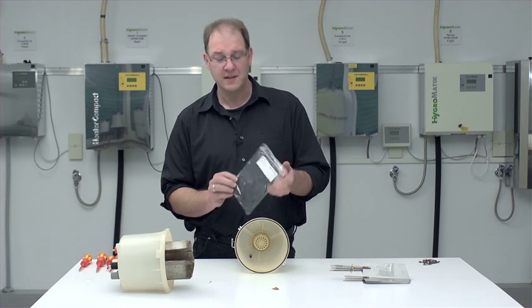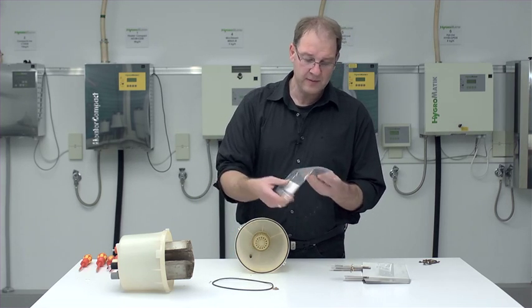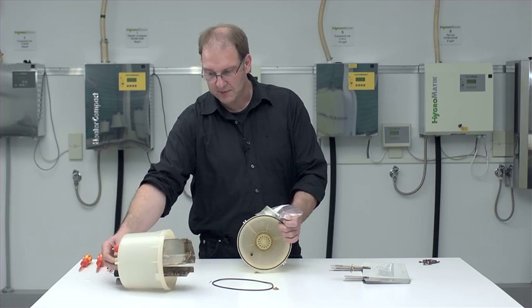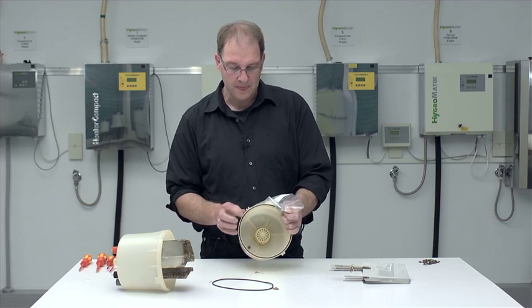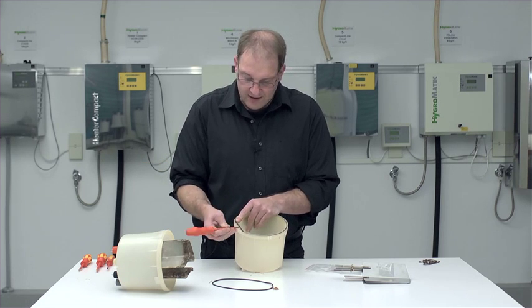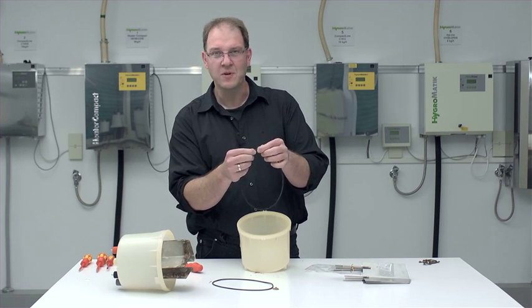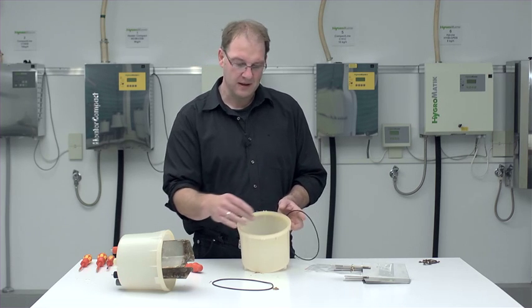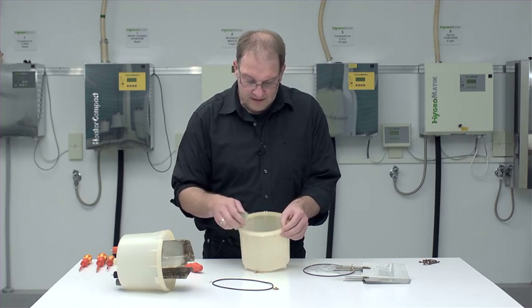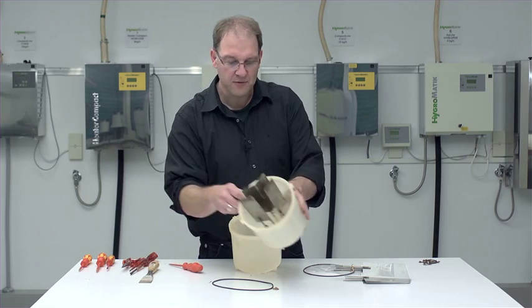In this o-ring set you will find one large o-ring for the cylinder flange and this is the one I am going to replace shortly. I can remove the o-ring from the cylinder flange quite easily. I just take a slotted screwdriver again, pick underneath it and there it is. You can feel it, it already is kind of misshaped and it would be difficult to return this o-ring back to its prior position. Before I insert the new o-ring, I need to make sure that the flange area, the groove where the o-ring is seated, is absolutely deposit free so small grains of buildup don't interfere with the seal later.